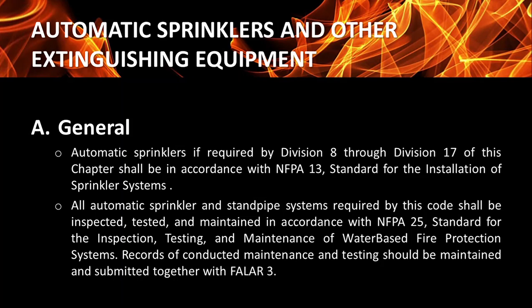Next is automatic sprinklers and other extinguishing equipment. In general, automatic sprinklers, if required by Division 8 through Division 17 of this chapter, shall be in accordance with NFPA 13, standard for the installation of sprinkler system. All automatic sprinkler and standpipe systems required by this code shall be inspected, tested, and maintained in accordance with NFPA 25, standard for the inspection, testing, and maintenance of water-based fire protection systems. Records of conducted maintenance and testing should be maintained and submitted together with FALAR 3.